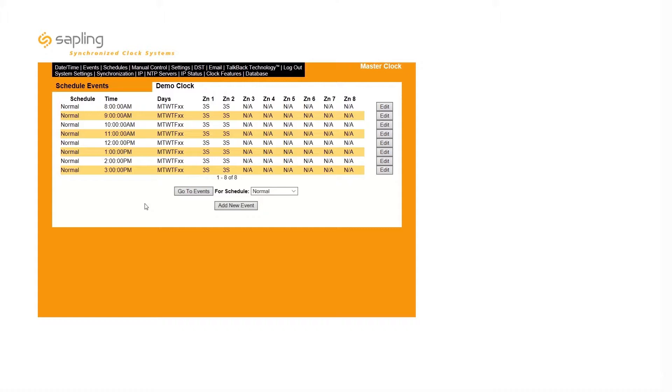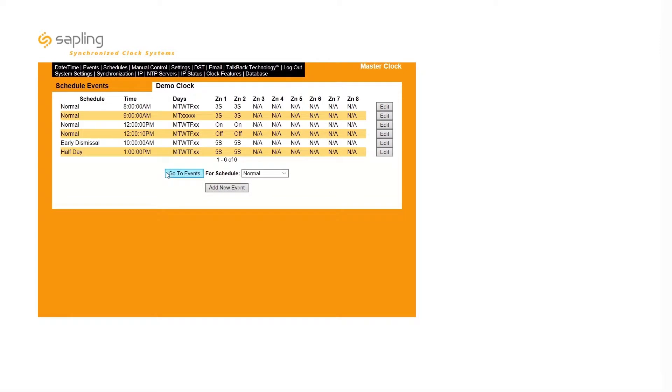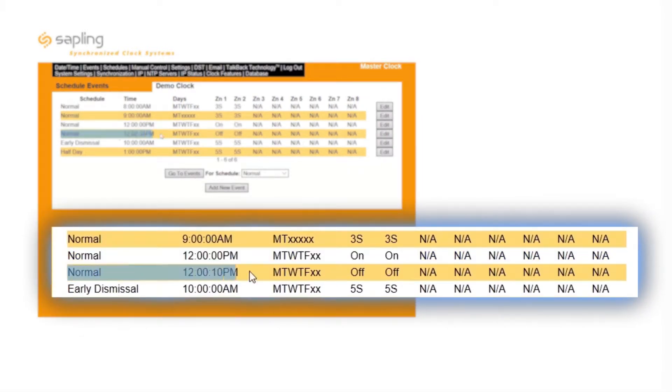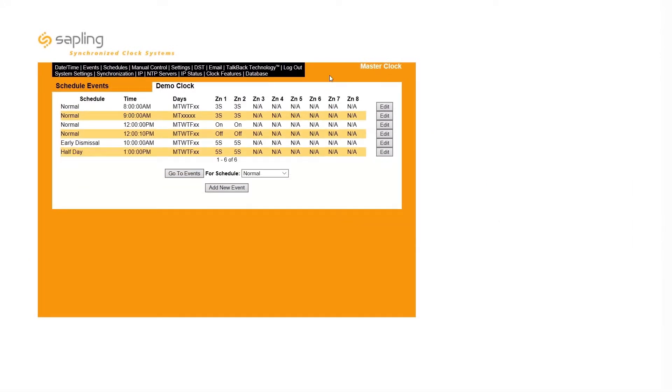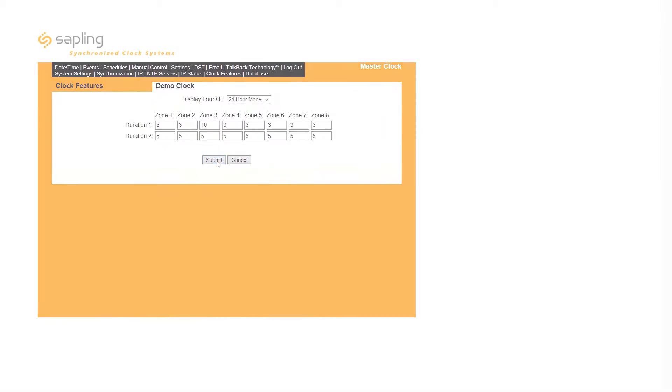For the school bell example, a user might create a schedule consisting of eight events, each timed one hour apart, which activates a bell relay for three seconds each time. As standard, a user can set a relay to close for three seconds or five seconds. The master clock's relays can be set to close for longer durations by creating two separate events, one to activate the relay and one to deactivate the relay, or by customizing the relay closure times in the Clock Features tab. This allows a user to program up to two custom closure durations for each programmable relay.